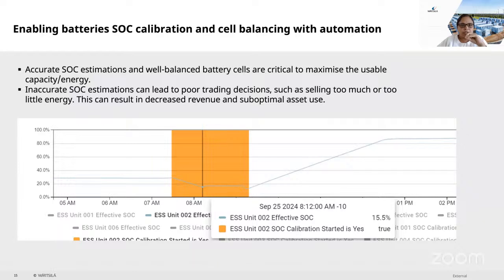So when the BMS's SOC calibration is triggered, these SOC estimations are corrected to provide a precise indication of the SOC. So the PPC should be able to enable a single unit or a group of units to enter this calibration mode automatically, so that the cell balancing happens and the SOC is corrected, while other units are meeting the market obligations. And in fact, even the unit that is getting calibrated and balanced is also available if needed to meet the market obligations. So that is the key.